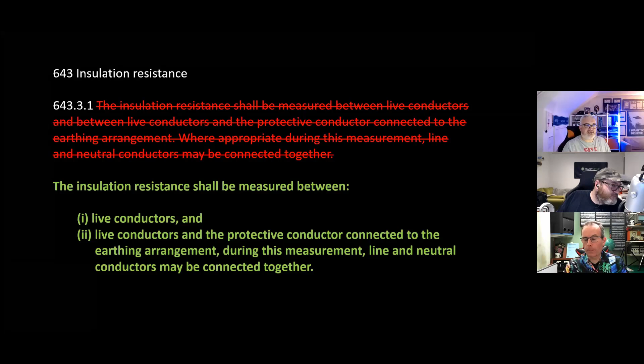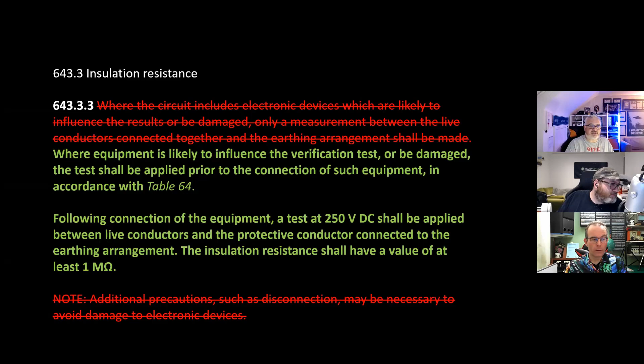643.3.3, insulation resistance. It used to state where the circuit includes electronic devices which are likely to influence the results or be damaged, only a measurement between the live conductors connected together and the earthing arrangement shall be made. Now it states where equipment is likely to influence the verification test or be damaged, the test shall be applied prior to the connection of such equipment in accordance with table 64. So yeah, basically try not to blow up connected equipment. Following connection of the equipment, a test at 250 volt DC shall be applied between live conductors and the protective conductors connected to the earthing arrangement. The insulation resistance shall have a value of at least 1 mega ohm. They have then deleted the note which says additional precautions such as disconnection may be necessary to avoid damage. They've just basically reworded it.